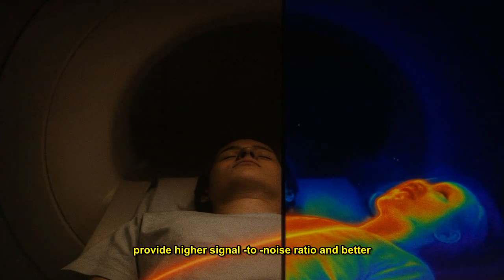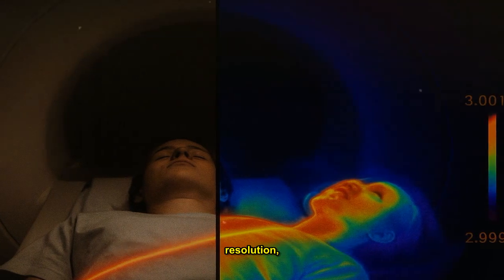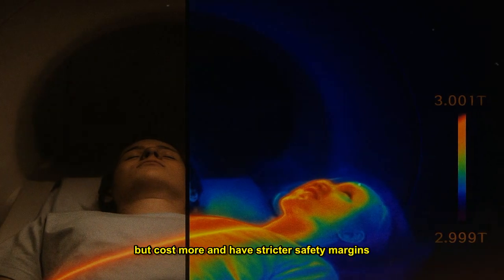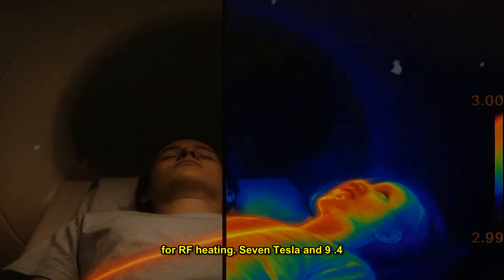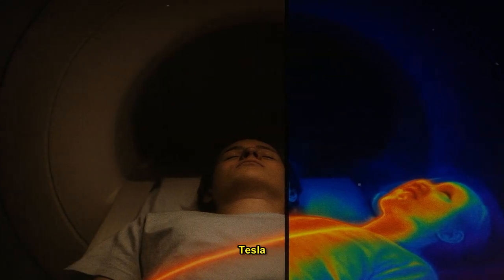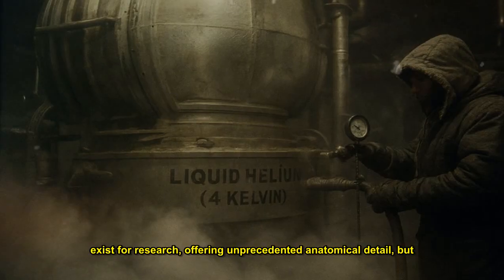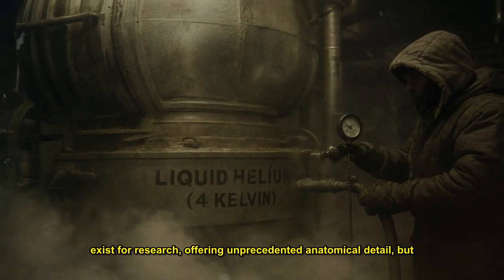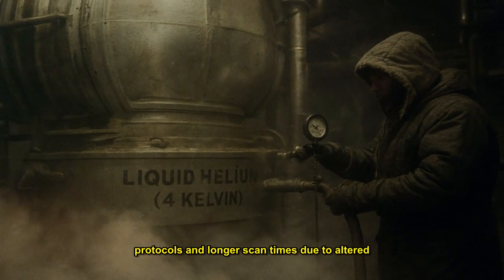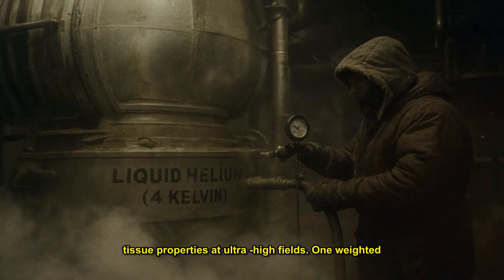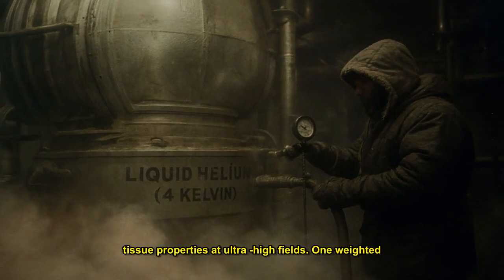3 Tesla scanners provide higher signal-to-noise ratio and better resolution, but cost more and have stricter safety margins for RF heating. 7 Tesla and 9.4 Tesla scanners exist for research, offering unprecedented anatomical detail, but requiring extremely careful safety protocols and longer scan times due to altered tissue properties at ultra-high fields.